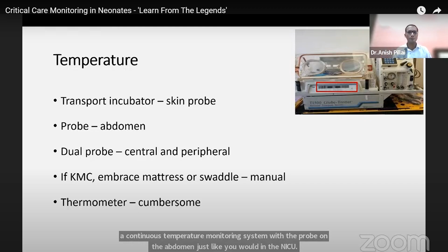Some of the incubators even have 2 probes, where there is one central temperature, like in the first talk we heard, and one peripheral temperature, which can be on the hands and feet. Because in cold stress, the baby's peripheral temperature will drop first and then the central temperature will drop. And if there is transport with kangaroo mother care or in an embrace mattress swaddle, then continuous temperature monitoring becomes very difficult, because you don't have the incubator. Then manual checks become very cumbersome, because you have to open the baby again and put an axillary probe. So from the temperature perspective, it is extremely important to maintain temperature. Use a continuous temperature monitoring system with the probe on the abdomen, just like you would in the NICU. And whether there is a single probe or a dual probe, either way, it should be a continuous display.